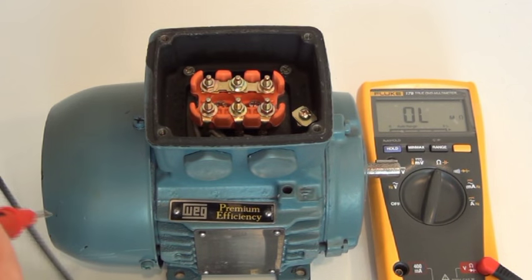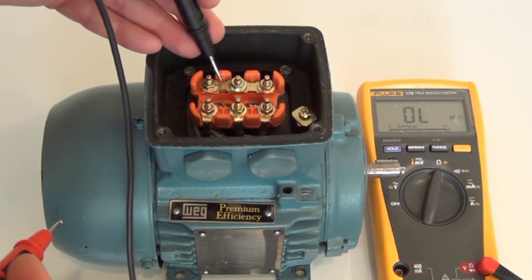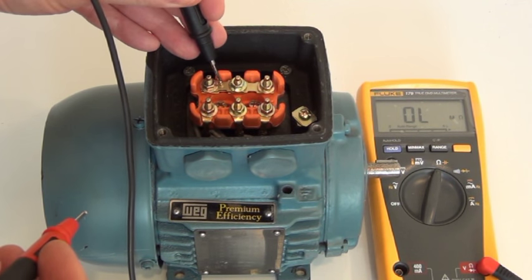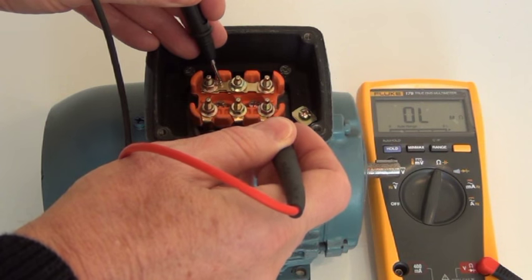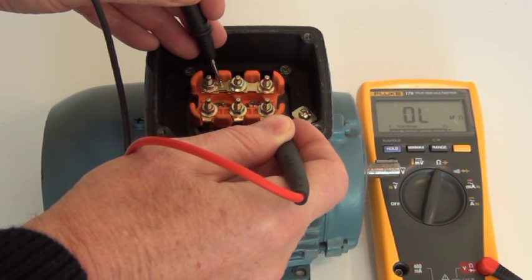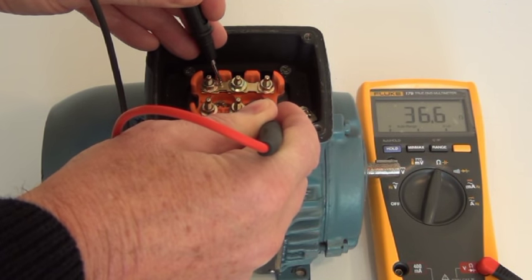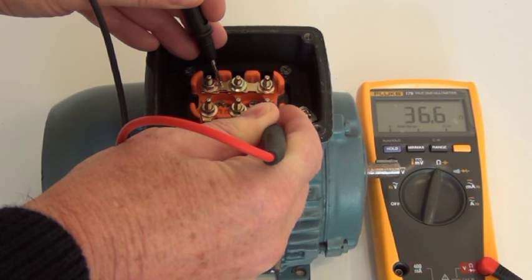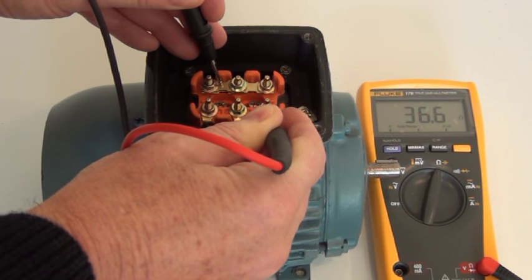I'm going to put my black lead onto the star point and then starting at U, which is this terminal, I've got 36.6 ohms. So I'll make a note of that.